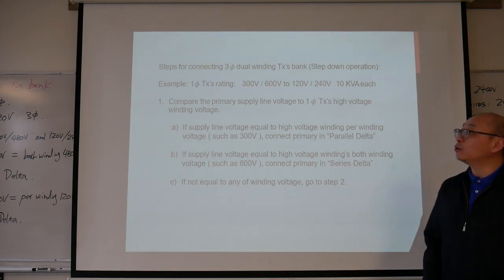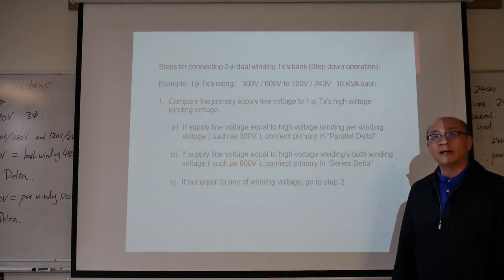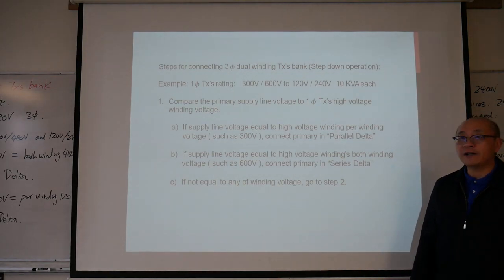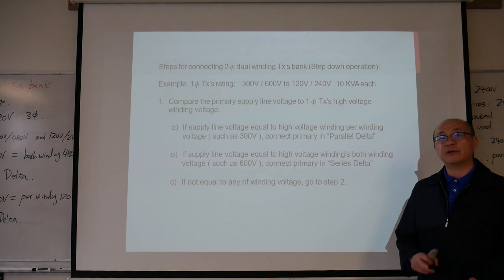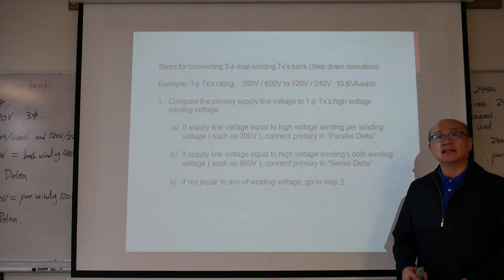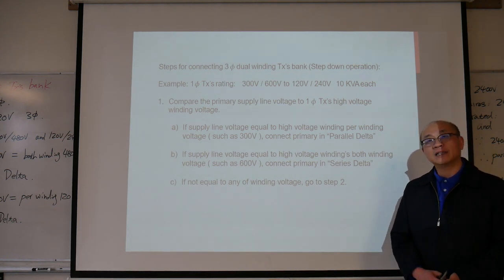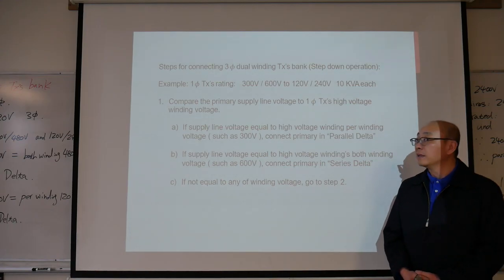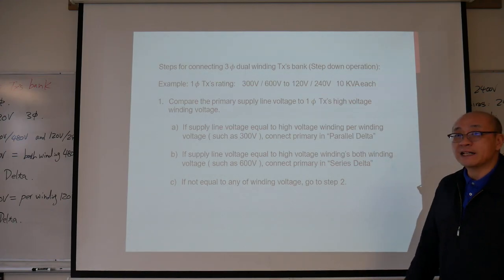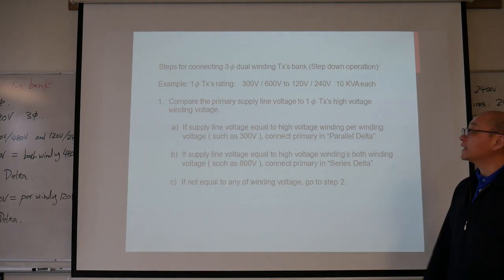When connecting a dual winding three-phase transformer, because in three-phase we have a Y connection and a delta connection, and because it's dual winding, we can connect them in parallel or in series. So the connection becomes much more complicated than the single phase. So here are some easy steps. I'll give you an example.